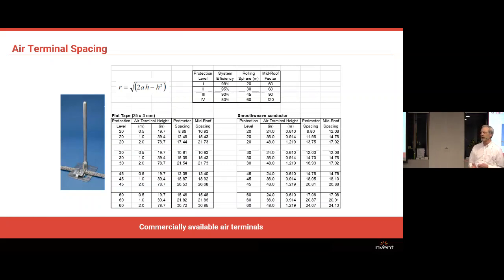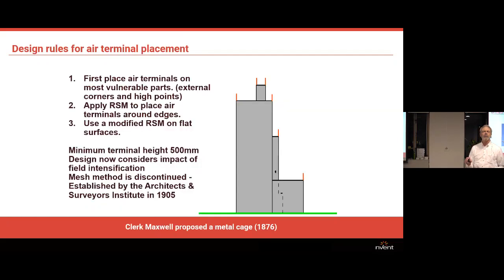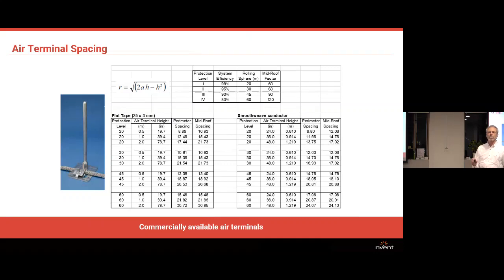Both systems have slightly different sized lightning rods, but let's see if this next slide has got more information. Okay, we use the rolling sphere method of placement, which is where you have a large ball, typically 45 meters radius, that's for protection level 3, or 90 meters diameter, and roll it along the structure. We'll say this is a building, sorry, roll it along the ground, and where it touches the building, then that building is deemed to be at risk. So you put in little rods there, and the sphere touches the rods and not the structure, and the structure is then deemed to be protected.